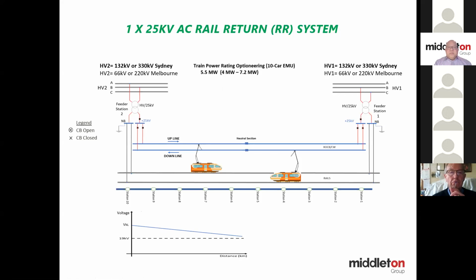And of course, today, that's not quite enough. We want to make sure its magnetic field is acceptable. And people are worried about exposure to magnetic fields. Am I going to get cancer or leukemia? Although it is not proven, the one that we most fear is people wearing pacemakers. So the high magnetic field may interfere with the pacemaker and cause malfunction. So all this needs to be taken into account when you're designing a system, not just being able to run your train and meet the timetable.